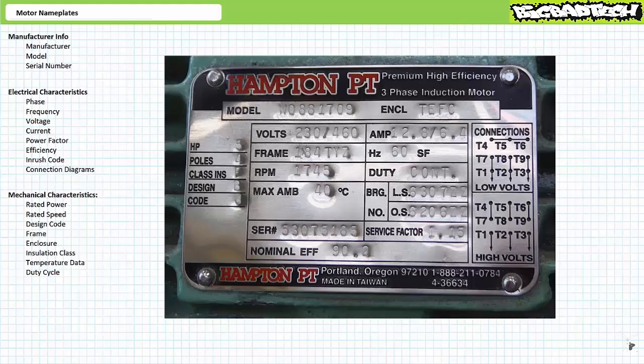The serial number, if it appears, is a unique identifier for that particular motor. Ideally, a manufacturer would be able to look up that serial number using their historical database and tell you when and where it was manufactured, whether it is or isn't under warranty, or whether that production run this particular motor was part of has any known faults or issues. Like, let's say, an annoying tendency to burst into uncontrollable flames. Here's an example motor nameplate.